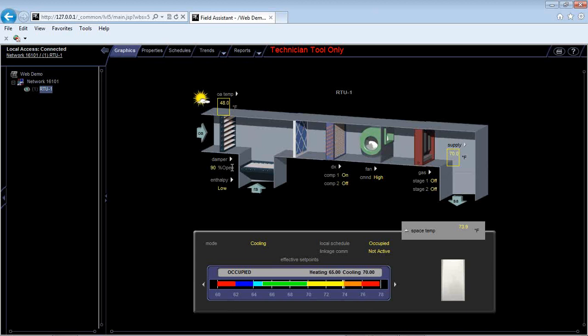So you can go through and fake the control program and tell it, hey, I need to do heating now, I need to do cooling now, and you can watch it run and watch the relays engage and the unit turn on. Okay, so that's the general basis of how you would go about testing the program with the controls contractor or with your mechanical contractor.